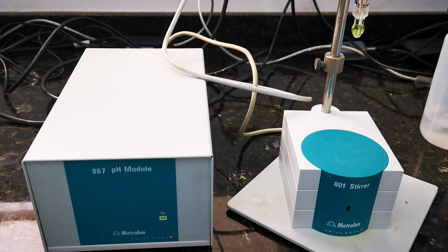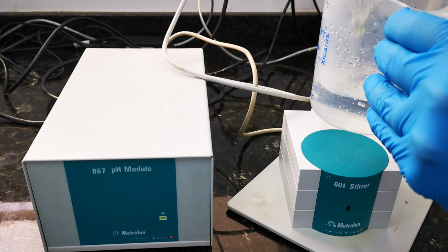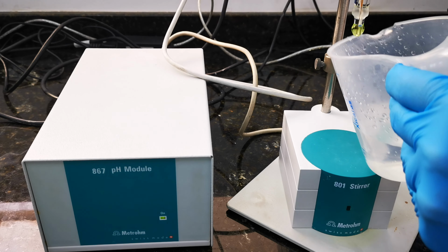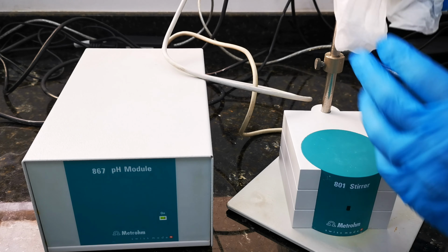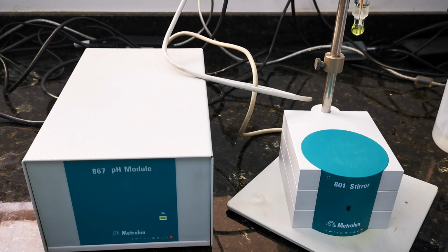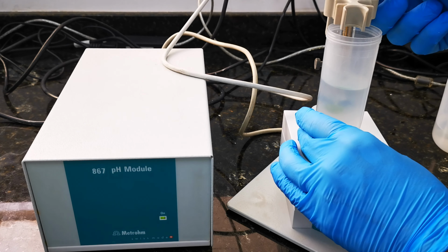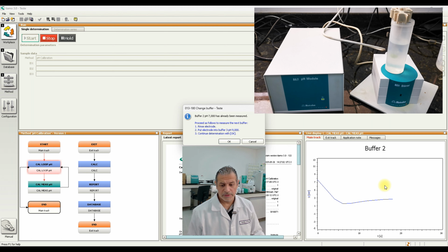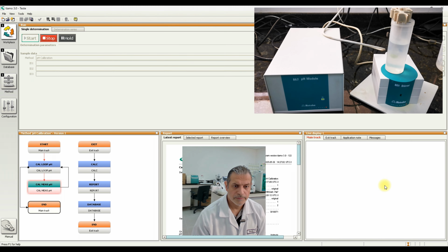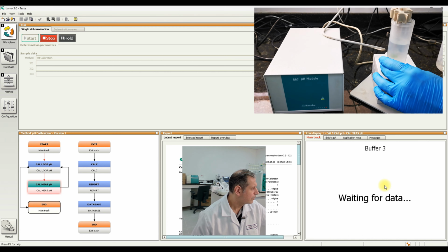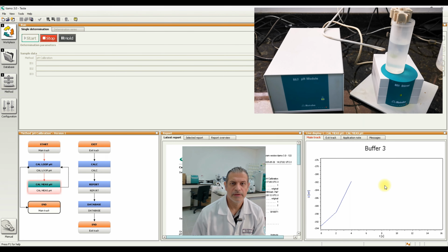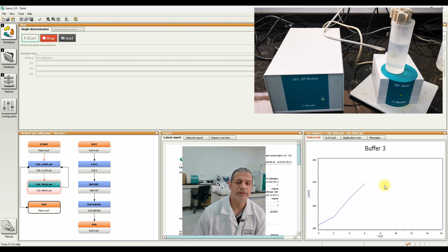Change again. Rinse the electrode. And now the pH 9. Remember, this is a very old electrode, but we have to reach at least 97%. The slope needs to reach 97% at least. So let's see what we are going to get at the final of the measurement.